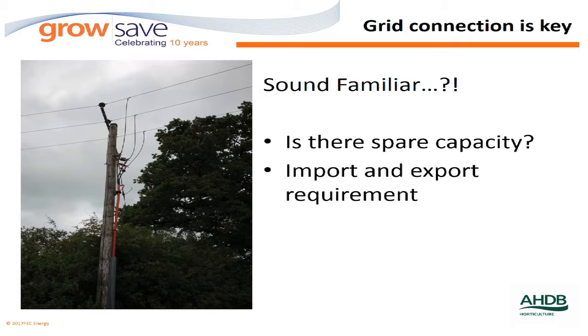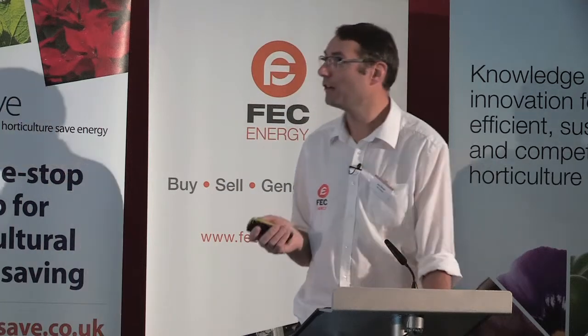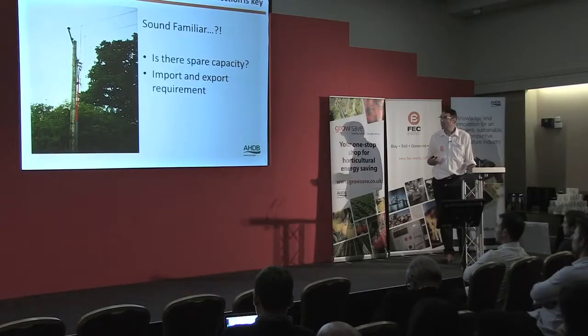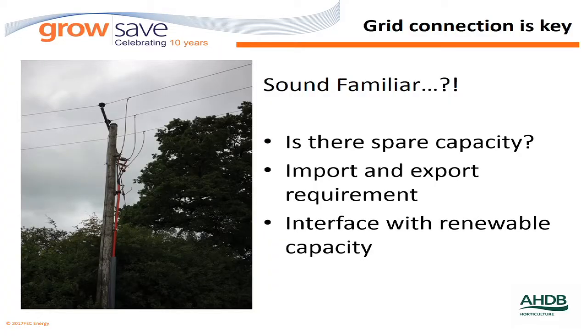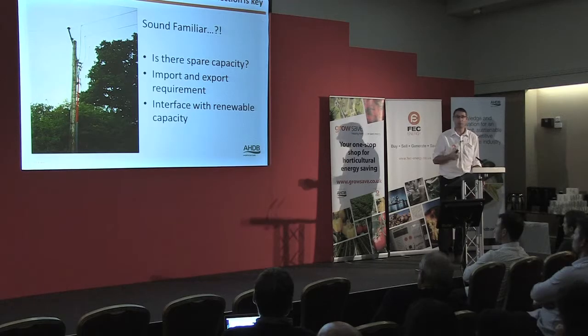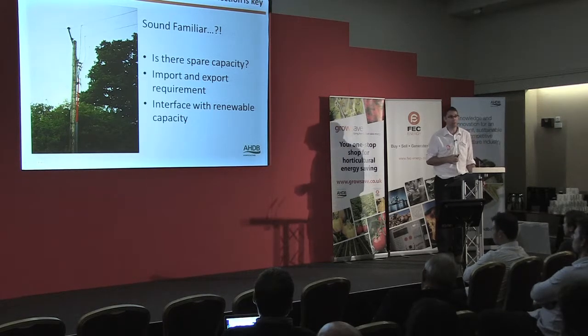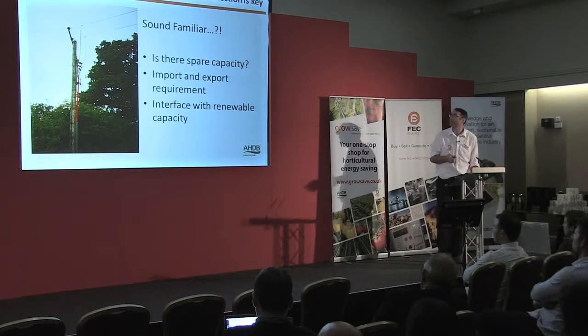Don't forget you need an import and an export requirement - you've got to charge these things up as well as discharge them, so they're not renewable energy systems in that regard. For example, you've got a PV system, you've applied for 2 or 3 megawatts of export capacity, but when you look at it, your peak capacity on export is only 1.5 to 2 megawatts - then maybe there's a bit of spare capacity there to have a battery system.